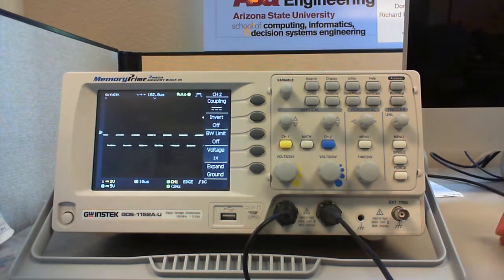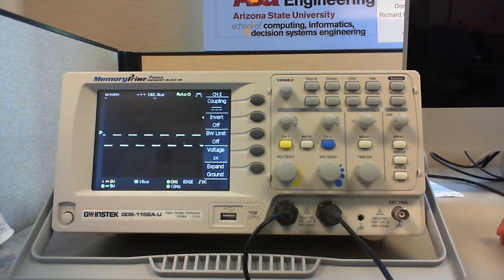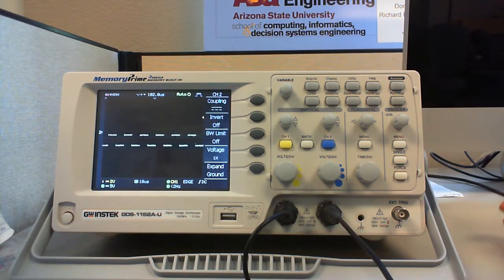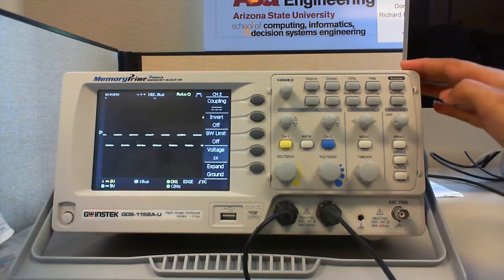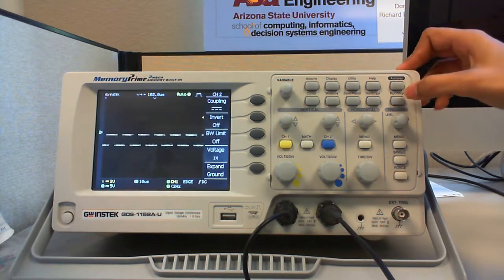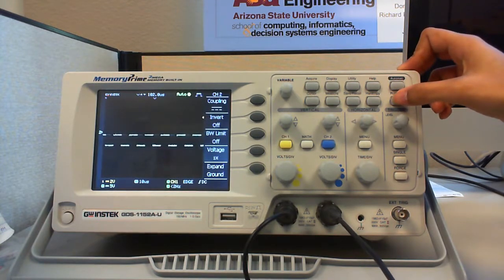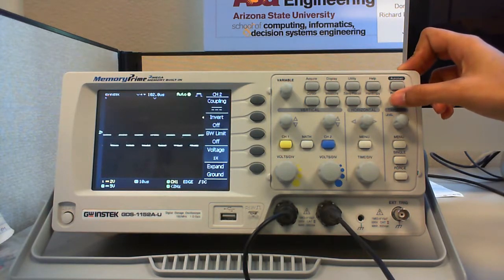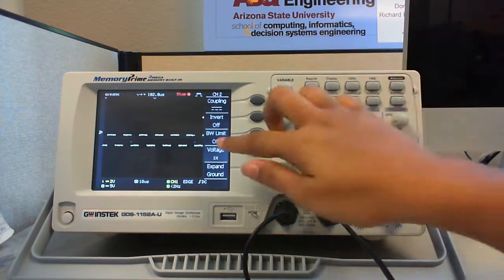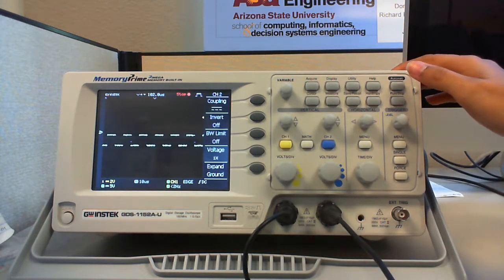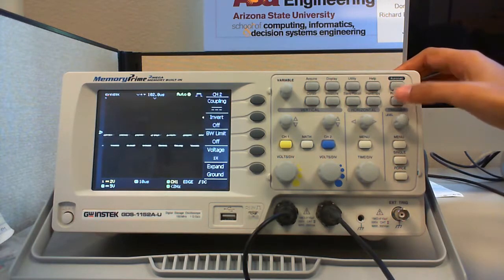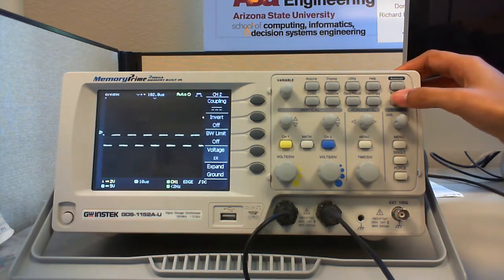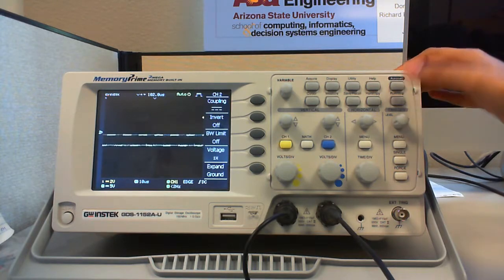Next, let us take a look at other important control knobs on the DSO. If you find it difficult to analyze a running waveform like this, you can stop it for a while and analyze it better. For that, you need to press the run or stop button to stop it and press the button again to resume it. The waveform is stopped and you can read it better. If you want to resume the running waveform, press the button once again. Now, let us stop the waveform for a while and analyze it.